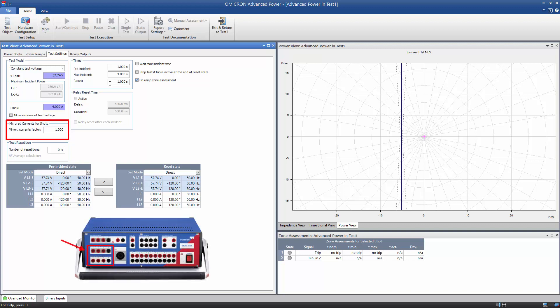The first current triplet of the CMC then represents the current fed into the differential protection relay, whereas the second current triplet represents the current leaving the differential protection relay.